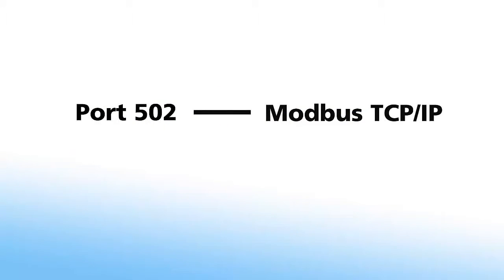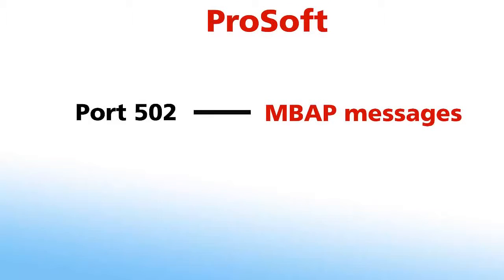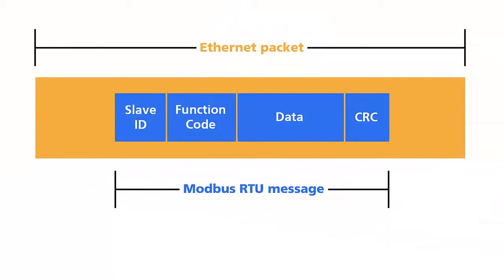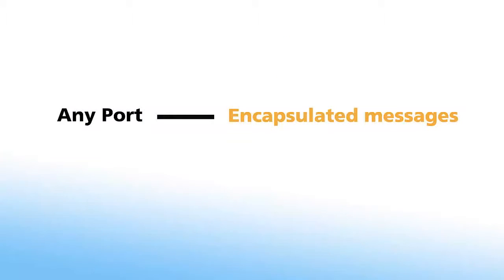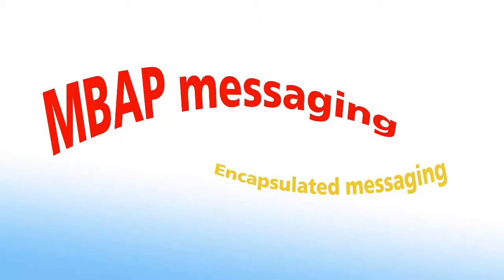Modbus uses port 502 for TCP IP communication. This is important if your data needs to go through a firewall. ProSoft uses that port for MBAP messaging specifically. Modbus serial messages can also be sent as regular RTU messages encapsulated inside an Ethernet TCP IP packet. Encapsulated messages can use any port, but ProSoft products are set to use port 2000 by default. Note that MBAP and RTU encapsulation are not compatible. Devices must be set to use one or the other.